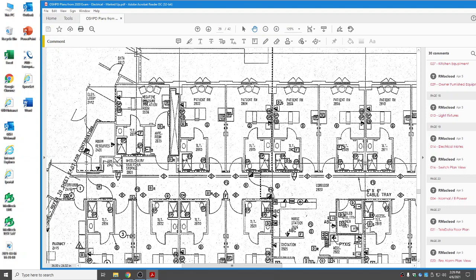Okay, so here we have, let's call it a corridor, and we're going outside through this corridor, and you can see they've got a dual egress door here. If you look for my little hand on the screen, you'll see there's an R, a fire alarm relay, and there is a D, a smoke detector, and then FS, that's a fire alarm speaker. Then this D with an R is telling you that we have a duct smoke detector on the return air duct system up above the ceiling here.